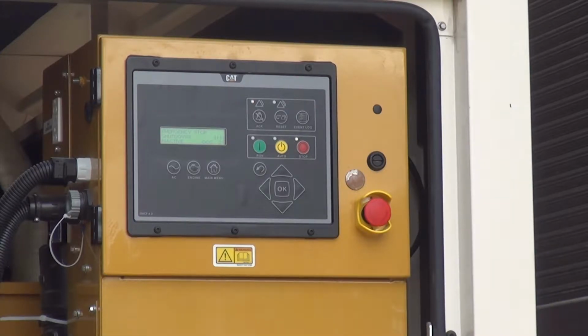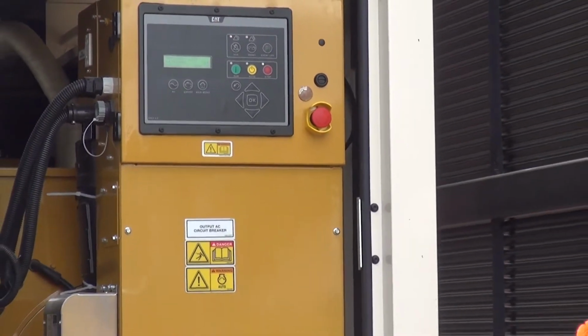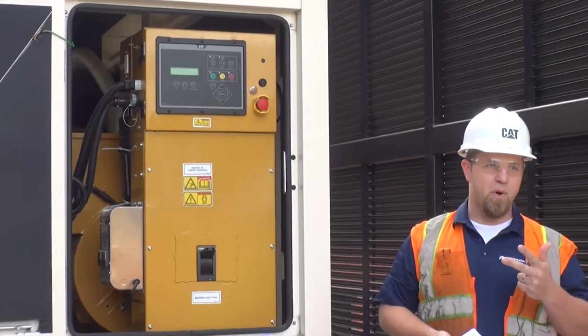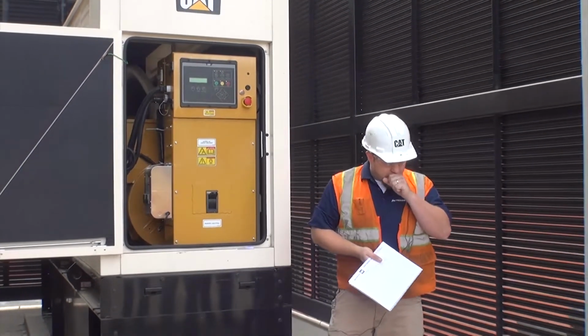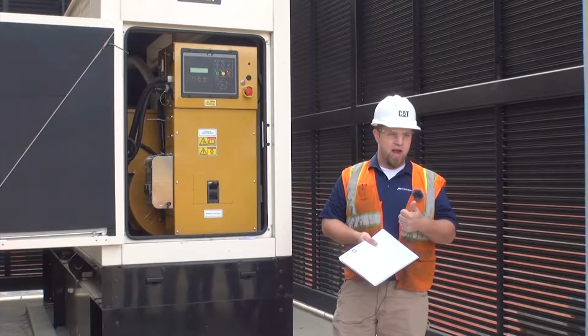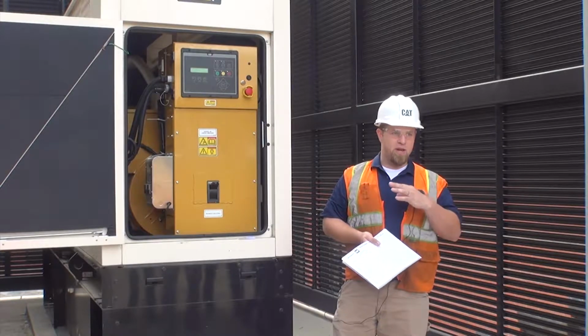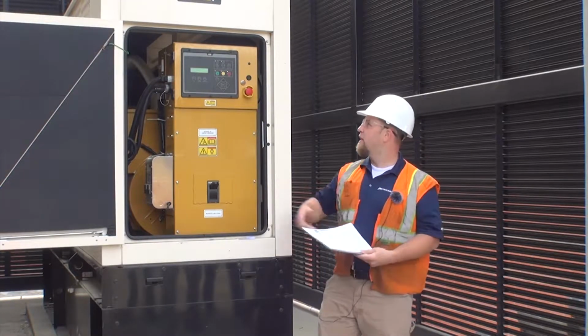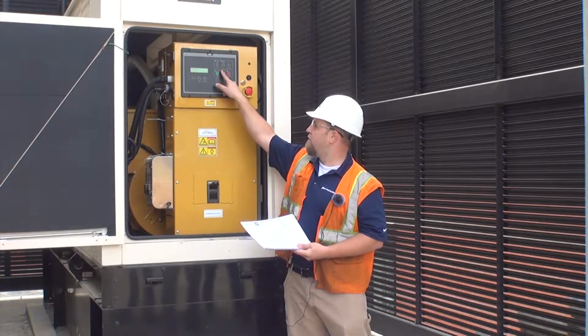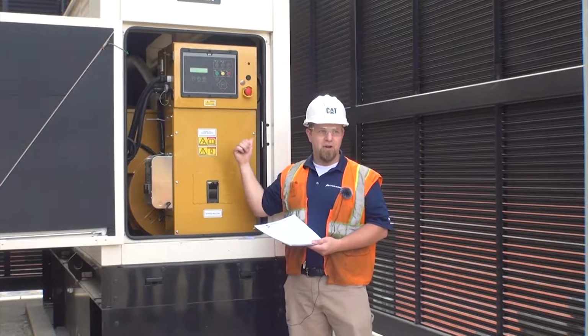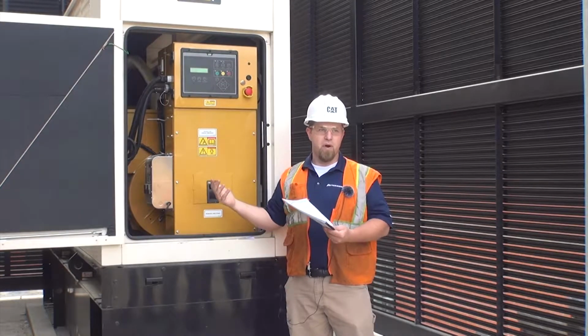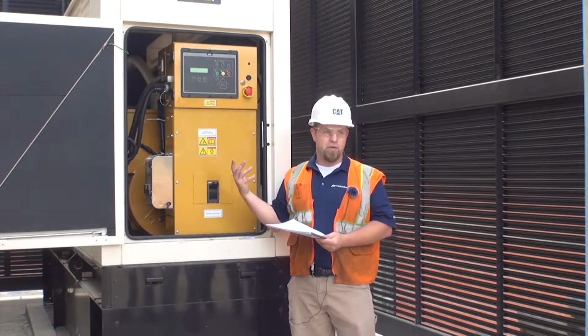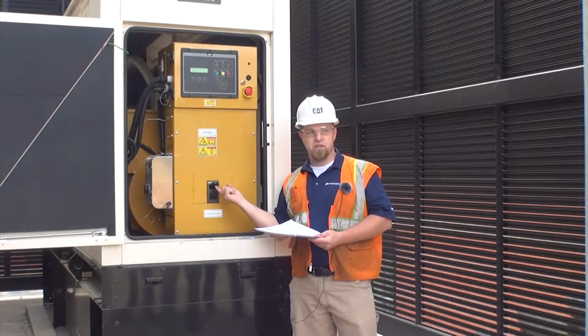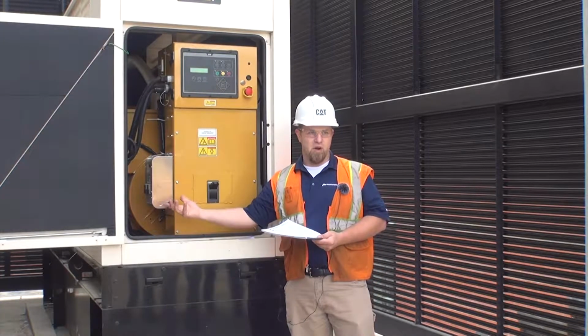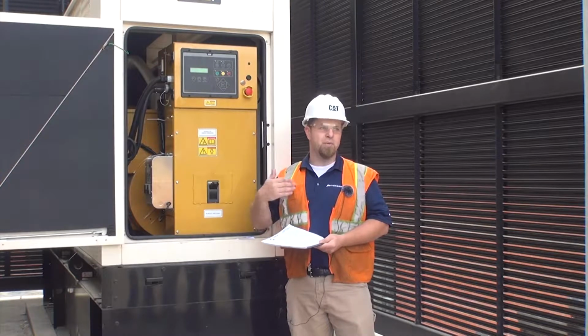If you guys can take anything from me today, take the ABCs: auto, breaker, charger. We broke it down as easy as we possibly could. The logic behind it is that if you're doing your weekly checks, you know you have fuel, you're doing your monthly transfers, and when you come out here and do anything on it, when you leave, make sure it's back in auto, your breaker is closed, and your battery charger is charging. That sets yourself up for the most success you can possibly have with this unit, because you know it's going to start, send voltage, and the batteries are charged enough to get it to start.